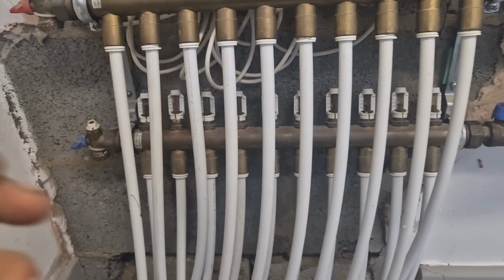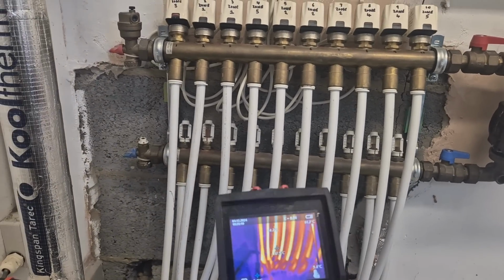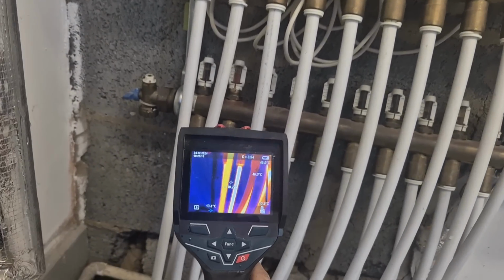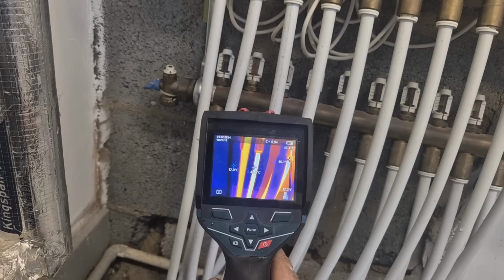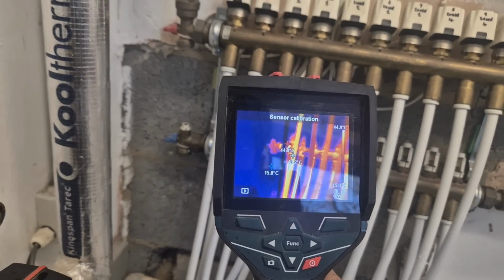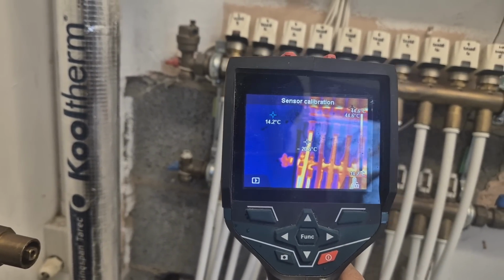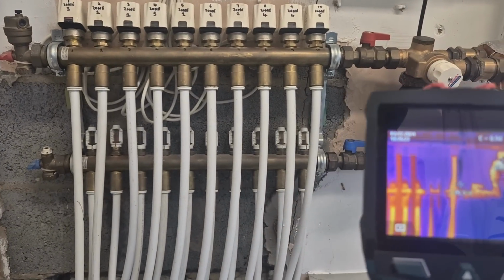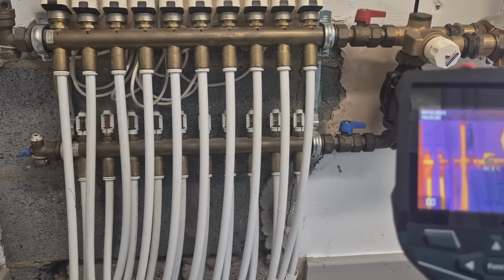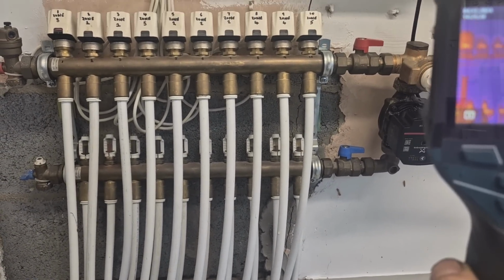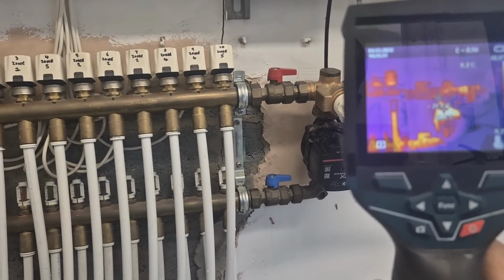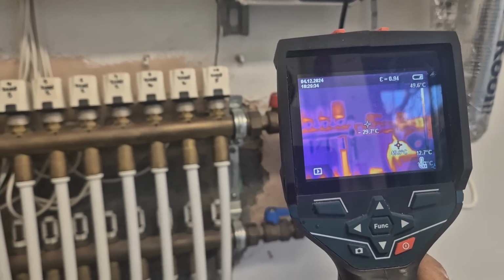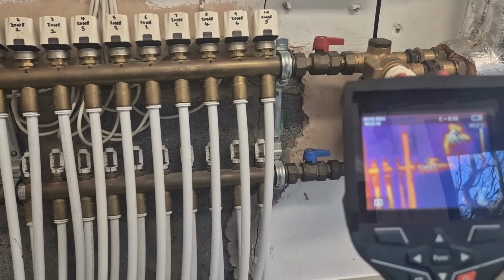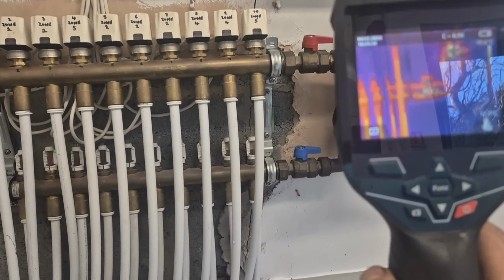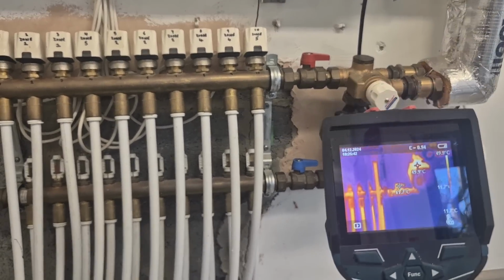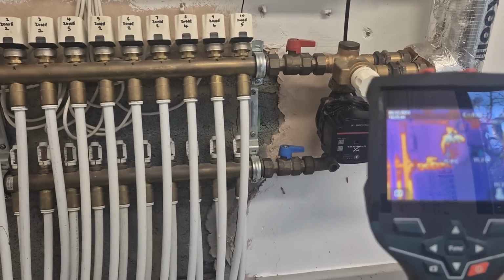Why is the flow getting on them in return? That one there. They put the pump on the wrong way around. That's 44. I think the pump's on the wrong way around. It looks like a new pump. I bet they put that on the wrong way around. 44 on the return. Oh. I bet they put that pump on the wrong way around. I see there's the old pump laying on the floor, but that flow should get hotter, and it's not. It's going through the return, so that's going the wrong way, that pump.